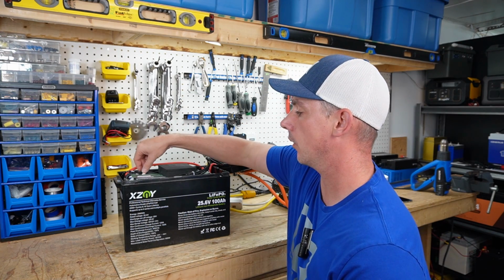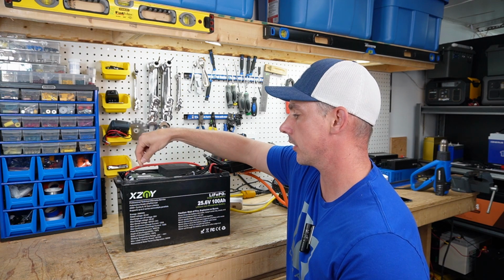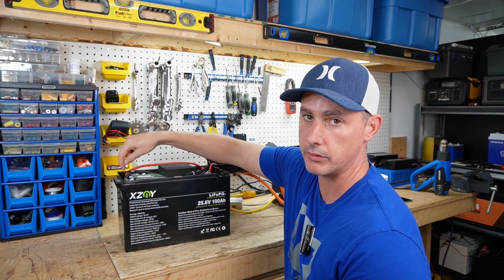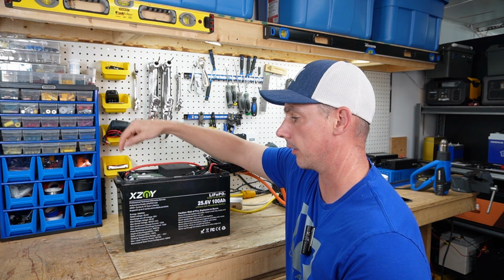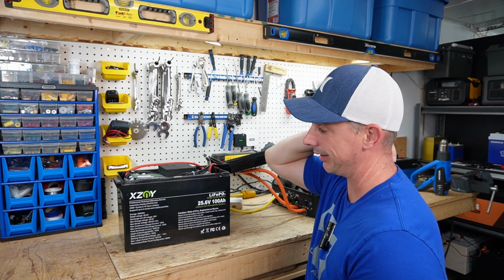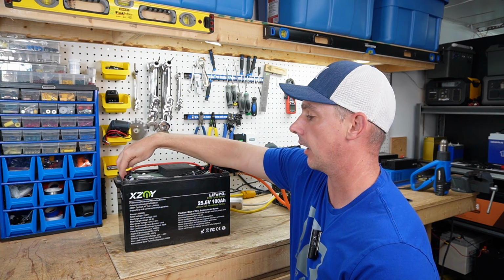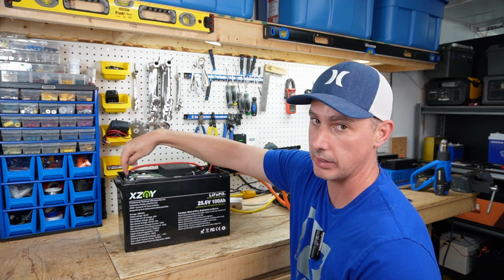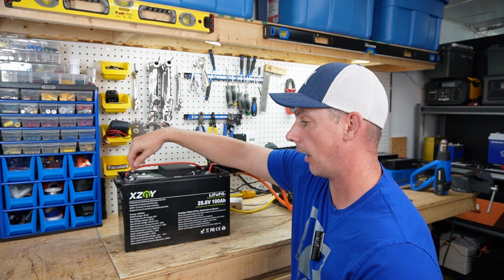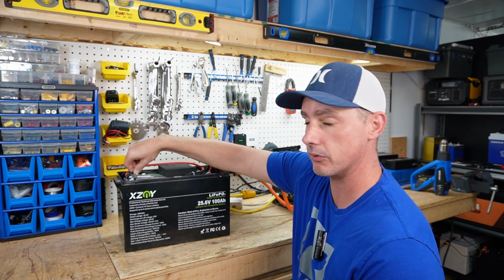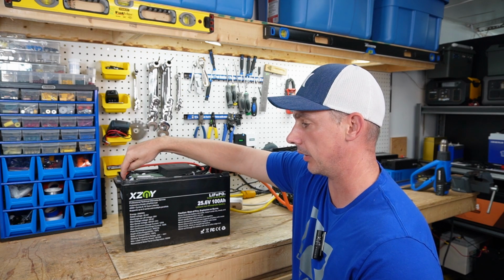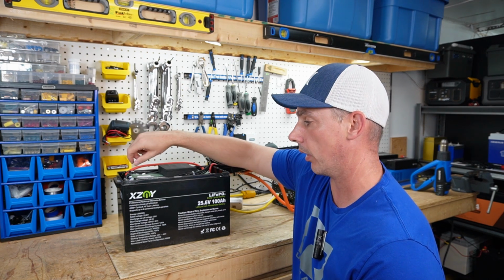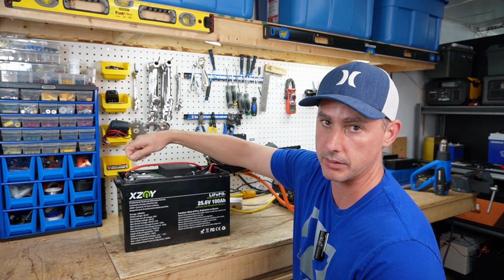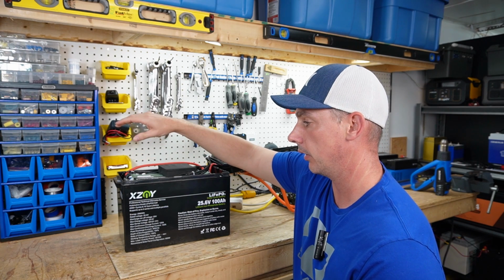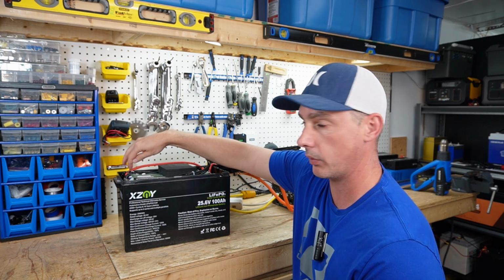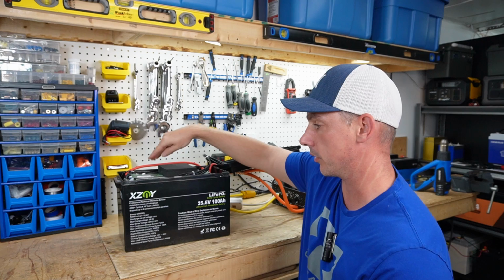Another thing I didn't like was these 12 gauge wires here, the 5 of them, running into a bolt in order to lengthen the wire down to the battery negative. I didn't like that, and they just kind of Mickey Moused it with heat shrink to cover the bolt. I have fixed it by zip tying it down so it can't move, and also putting a bit of tape to secure it. But what could happen is it could wiggle side to side, and it could rub and cause contact with one of the positive terminal posts here.